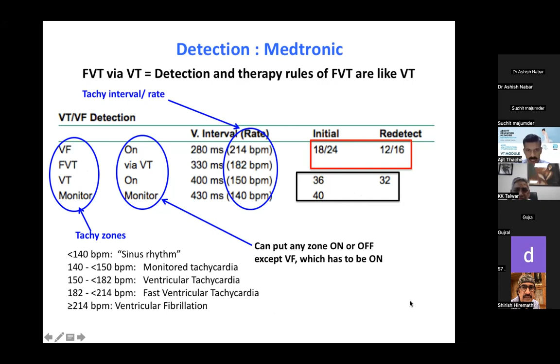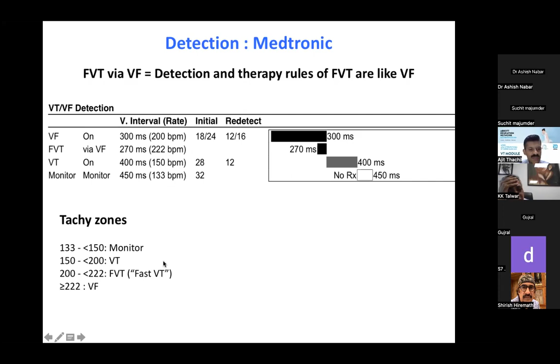Whereas if you program like this, FVT via VF, this means that anything between 133 to 150 is monitor. 150 to 200, so you read from this number to this number, 150 to 200 is called a ventricular tachycardia. It needs 28 beats. 200 to 222, you have to read from top to bottom, 200 to 222 is called a fast ventricular tachycardia. And the diagnostic criteria for fast ventricular tachycardia here will be 18 out of 24. Now, what is this 18 out of 24?